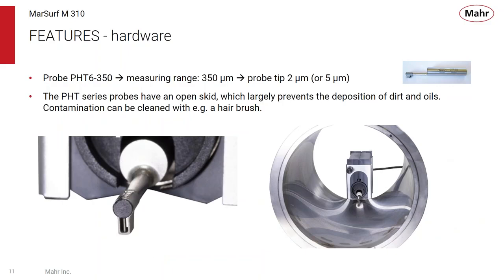The standard probe, which Mahr uses across many products, can come in a 2 or 5 micron radius tip. You can see from the pictures that this is a flow-through design of probe. It's an open skid system, but because it's open, if any dirt or oils or contamination gets in there, you can clean that out with a fine hairbrush. This probe can fit into a lot of small places, IDs and ODs, etc.